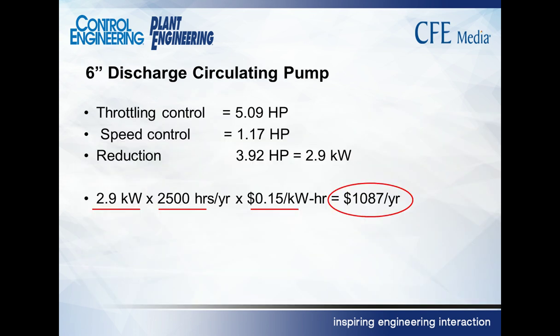Sure. We started with 5 horsepower. If we throttled it down, we got it down to about a little over 1 horsepower if we use speed control. That's a reduction of 3.9 horsepower. We can convert horsepower to kilowatts, both measures of power, at 746 watts per horsepower. So that's equivalent to 2.9 kilowatts of power. And let's say we're running this 2,500 hours a year. That's just a little bit over one 8-hour shift for a year.